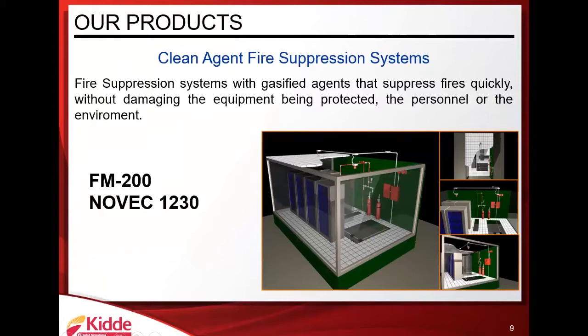As soon as you have the certification, you also get the ability to buy the license key for the software. In the meantime, if you don't have the license key or the certification, you can always go through Full Protection. If you have a project where you need a design for a clean agent fire suppression system, you can send them all the data. Normally what we ask for is the dimensions of the area, the temperature, the location - how high it is from sea level - and what type of equipment we're protecting. With that information, you forward it to Full Protection, and they can get in touch with me, and we help you with the design in the meantime, or while you get certified on our products.